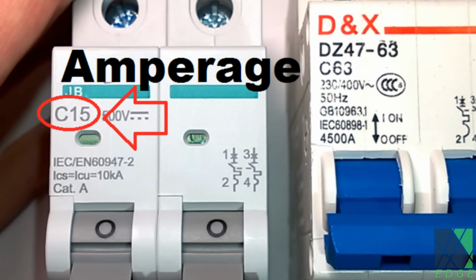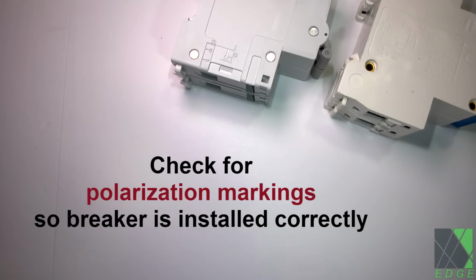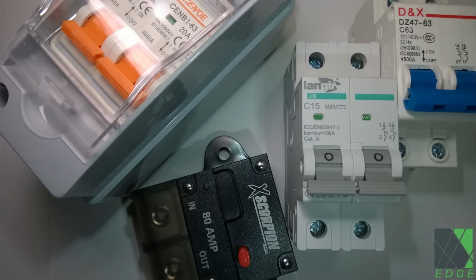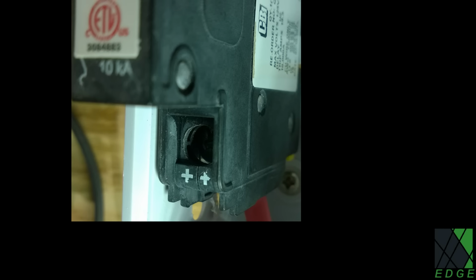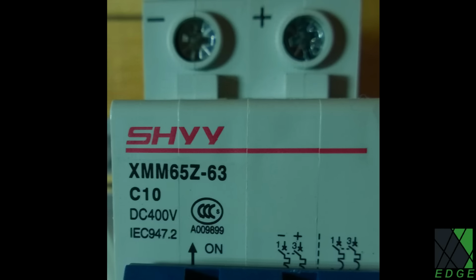This circuit breaker is rated at 15 amps, but sometimes that's not the whole story. Again, it's important to read the specifications and choose the right breaker for the job, because there are different versions which behave differently by design. Some circuit breakers are polarized, meaning they have a positive and negative polarity. Be sure to check the markings and specifications to ensure the breaker works correctly. Warning: if the DC circuit breaker is polarized and you install it incorrectly, it will lose its ability to protect the circuit and break arcs.